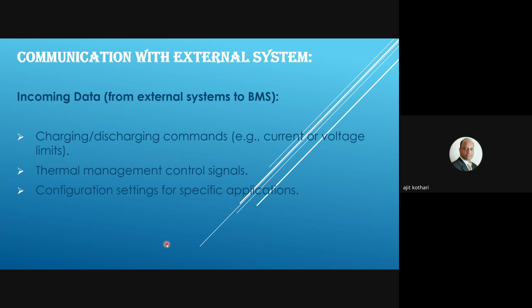Another application is energy storage systems. The battery bank is connected to the PCS, we can say inverter, and that inverter output is connected to the grid. For EMS it is very important - like VCU in case of a vehicle, EMS is the energy management system where the information of the battery bank is given to it. EMS will understand the reservoir or capacity available with the battery bank, and from that it can switch to the battery bank whenever it is required. So that information is again important from an application point of view.